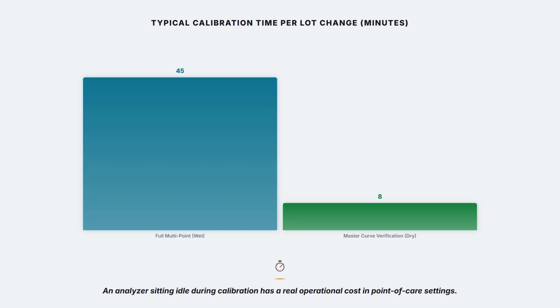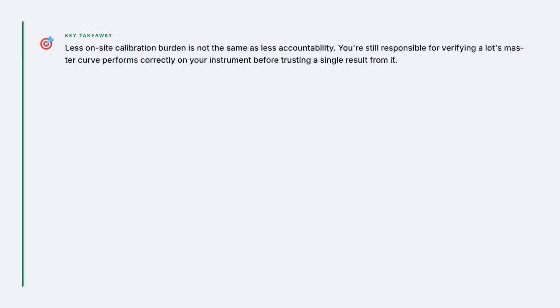The calibration level principle worth carrying: less on-site calibration burden is not the same as less accountability. You're still responsible for verifying that a lot's master curve actually performs correctly on your instrument, with your patient population, before you trust a single result from it.